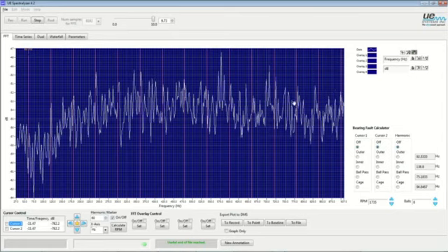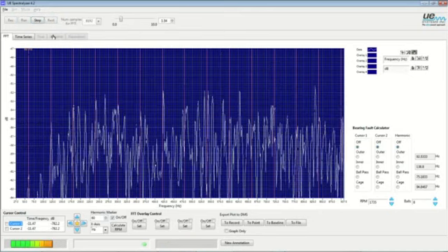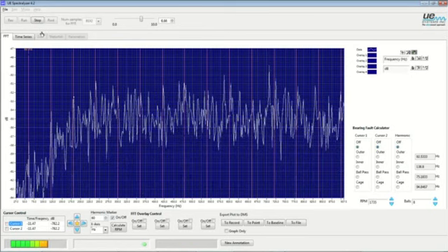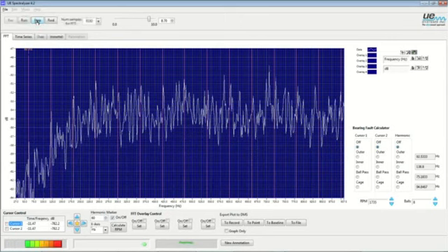So again, a couple of 60 hertz peaks, although not big. It changes over time with the recording. We'll play this one more time. So the first signature of a tracking event using a contact measurement is verified in this spectrum. We have several 60 hertz peaks, and there is an abundance of frequency noise that's taking place throughout the recording.